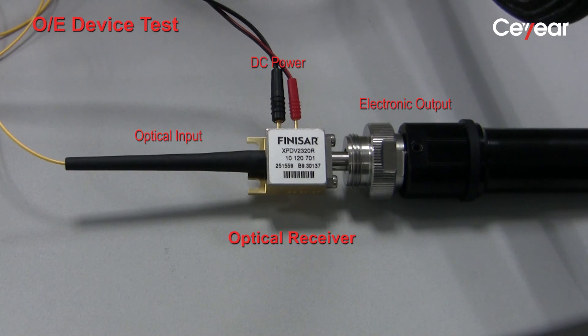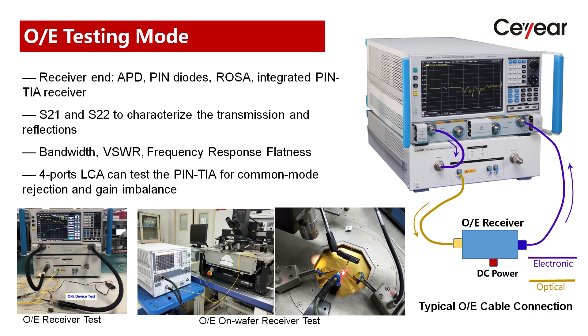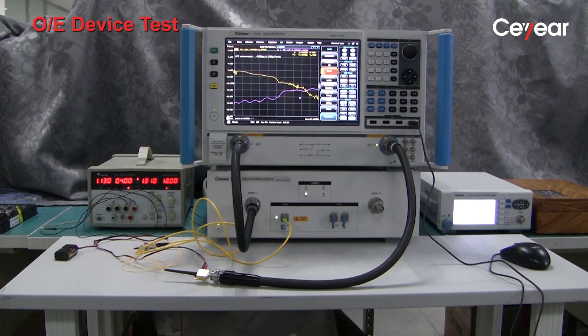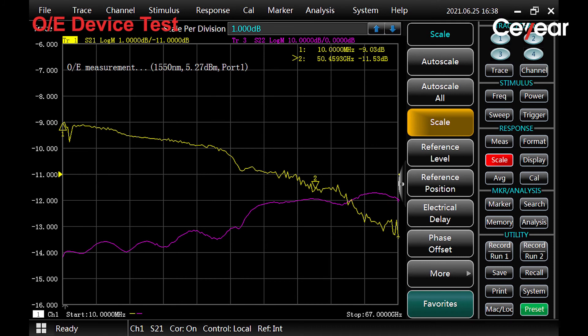Now let's test an optical receiver, a typical OE device. We connect the system cables and optical receiver as shown on screen. In OE measurement mode, we follow the system's instructions to make the necessary calibration. Then we can read from the screen that this receiver's 3 dB bandwidth is about 50 GHz.